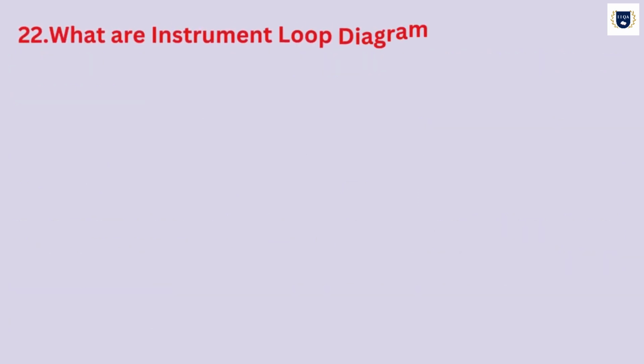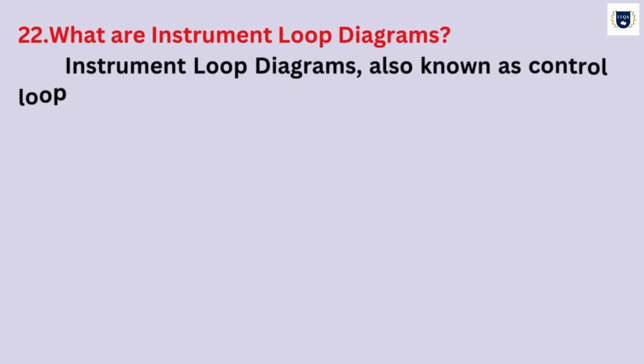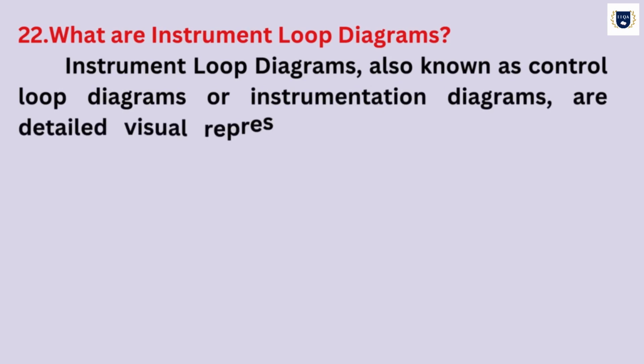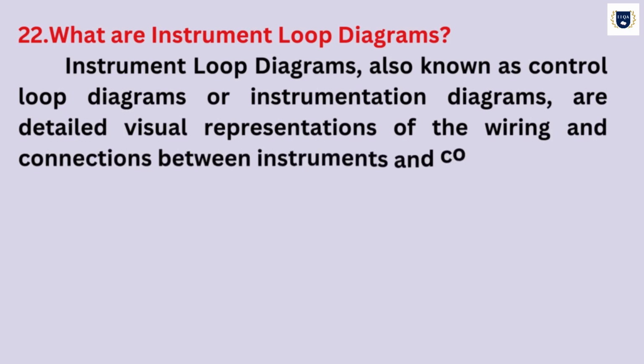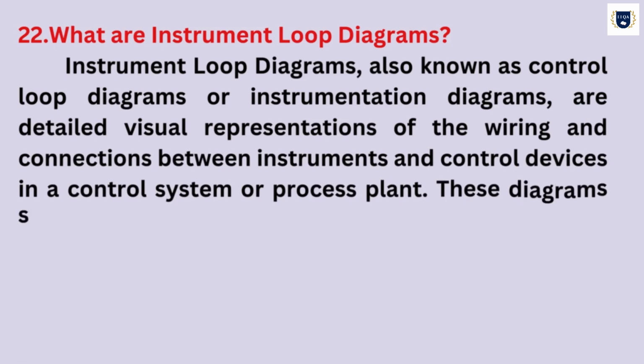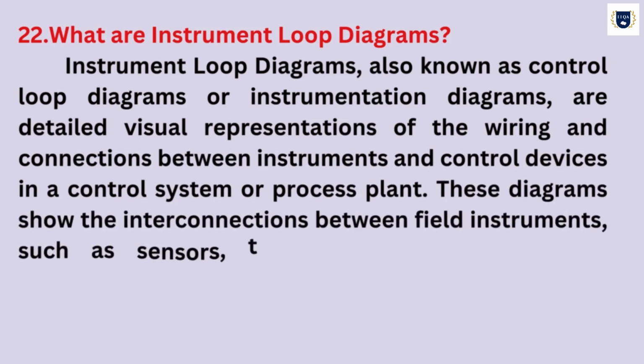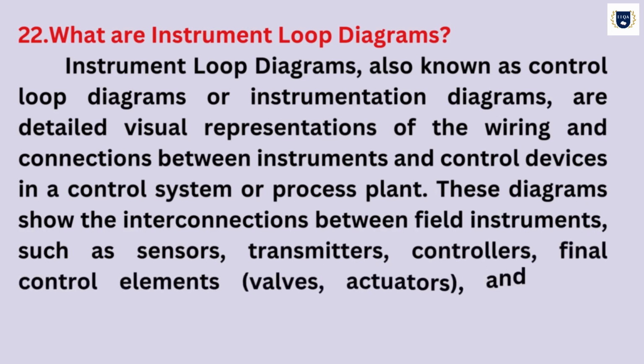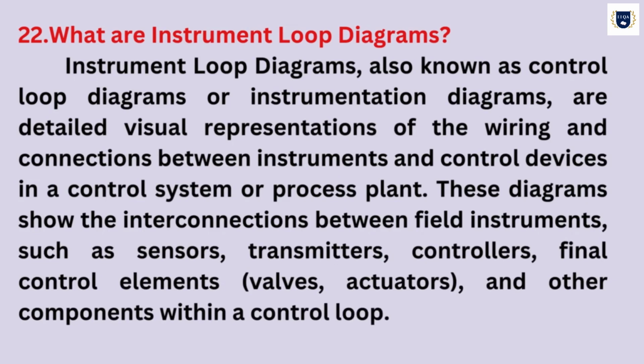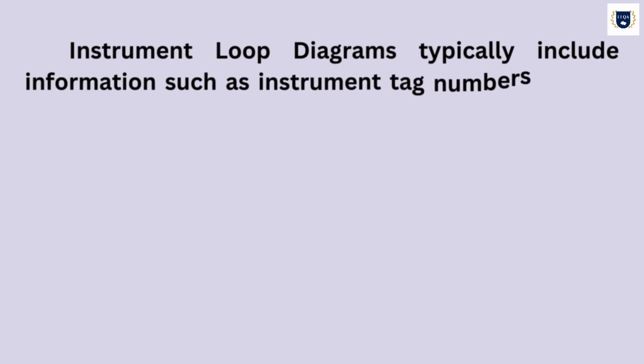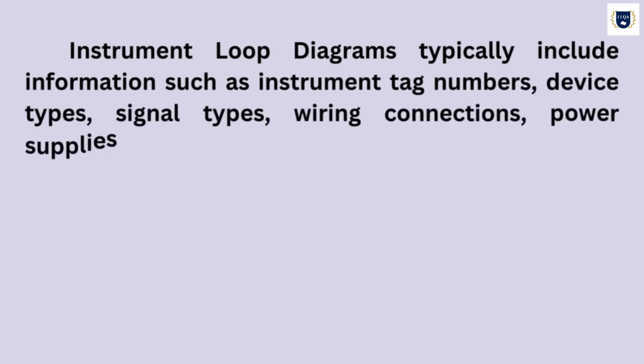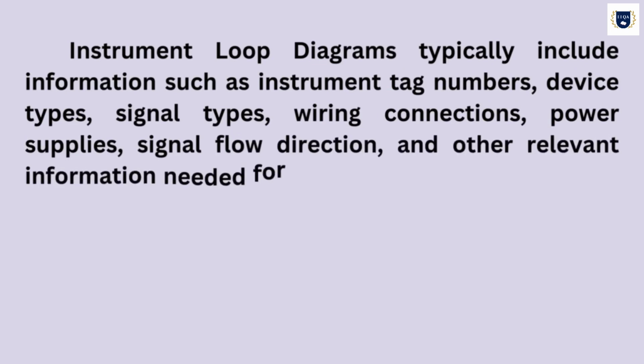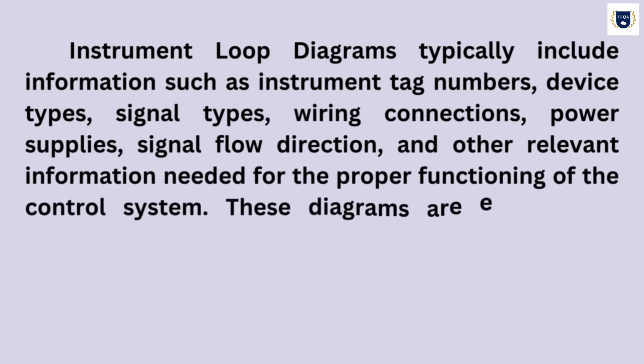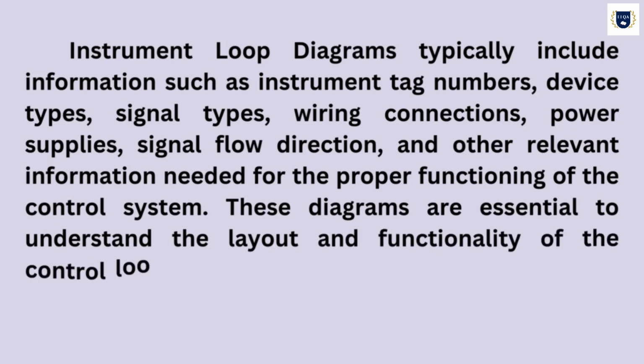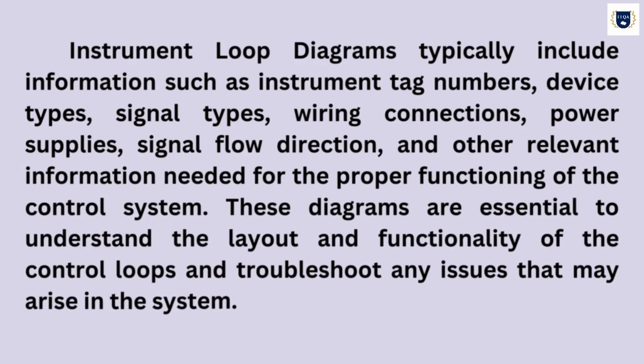What are instrument loop diagrams? Instrument loop diagrams, also known as control loop diagrams or instrumentation diagrams, are detailed visual representations of the wiring and connections between instruments and control devices in a control system or process plant. These diagrams show the interconnections between field instruments, such as sensors, transmitters, controllers, final control elements, valves, actuators, and other components within a control loop. Instrument loop diagrams typically include information such as instrument tag numbers, device types, signal types, wiring connections, power supplies, signal flow direction, and other relevant information needed for the proper functioning of the control system. These diagrams are essential to understand the layout and functionality of the control loops and troubleshoot any issues that may arise in the system.